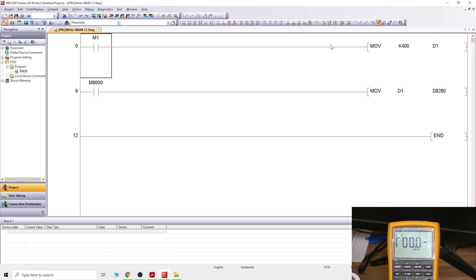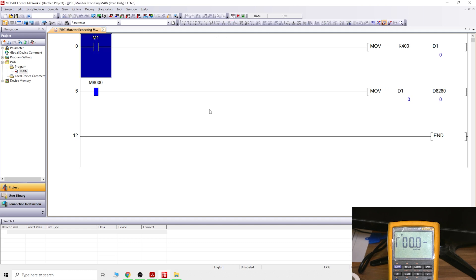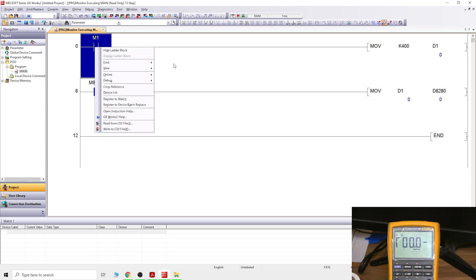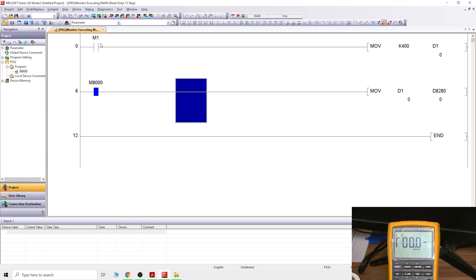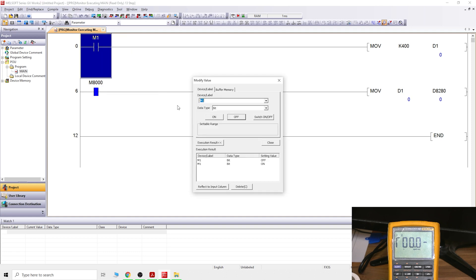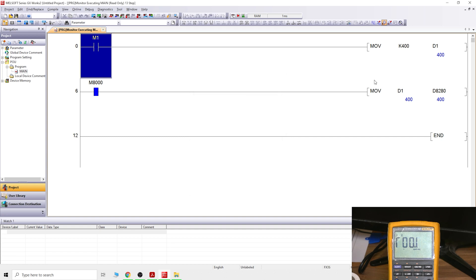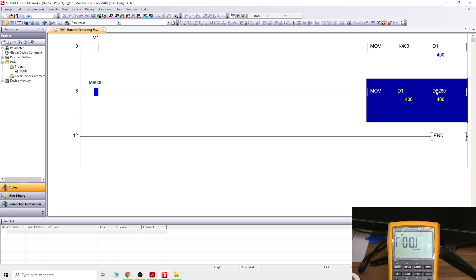Once that's done, we are going to be checking out the values. Let's go into monitor mode and let's turn on M1. As you can see, I have transferred that value into D1, and D1 has transferred value into D8280, and that represents, if you can see on the meter, one volt.